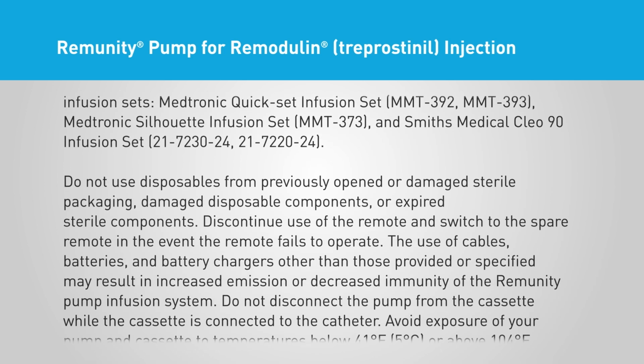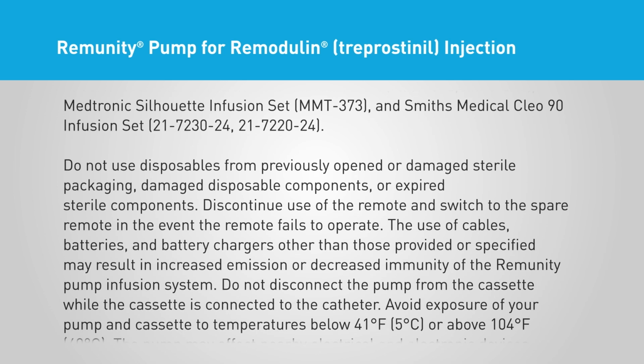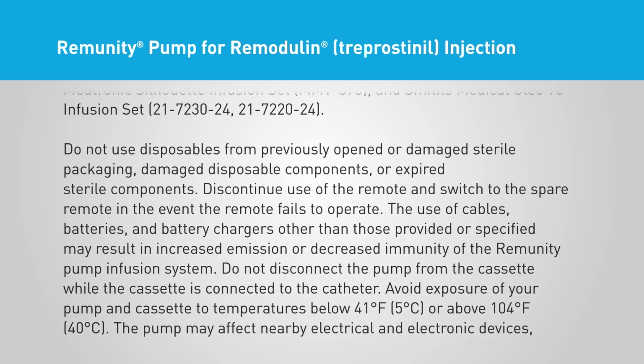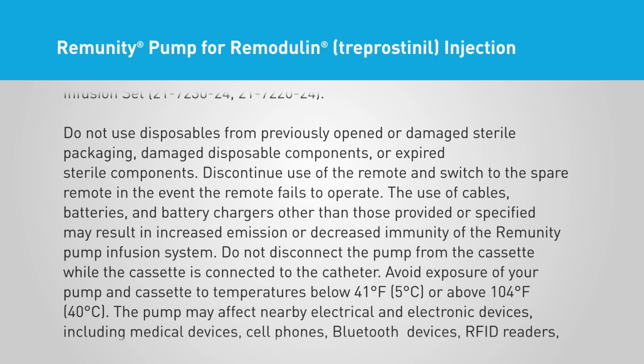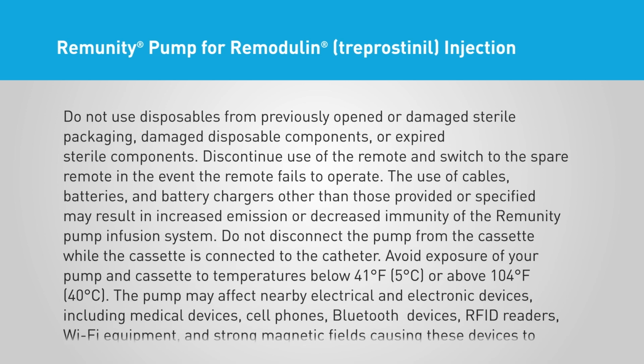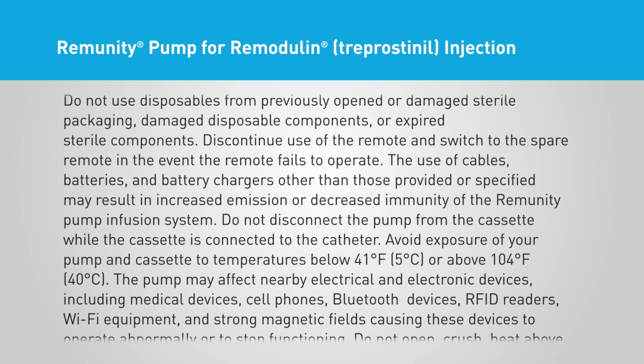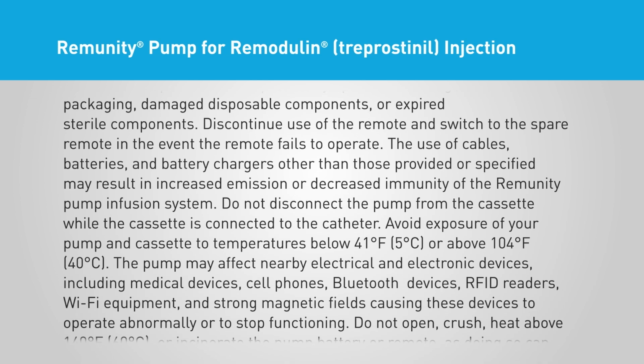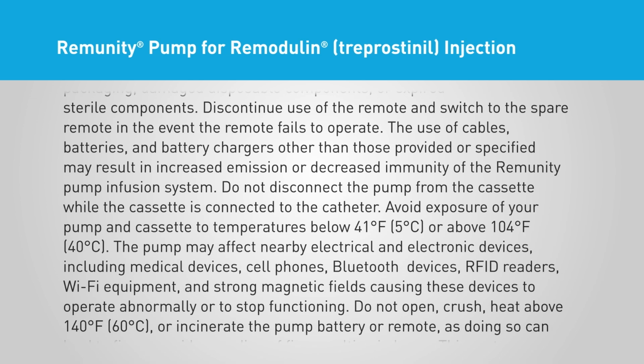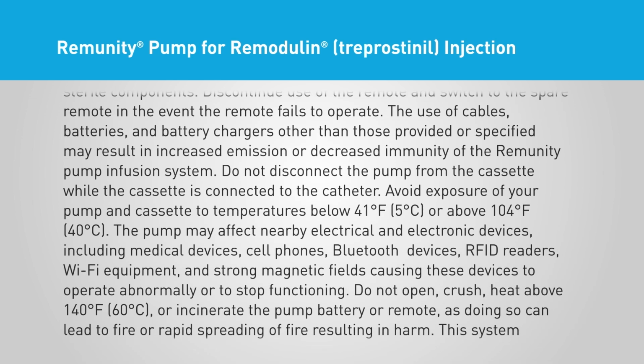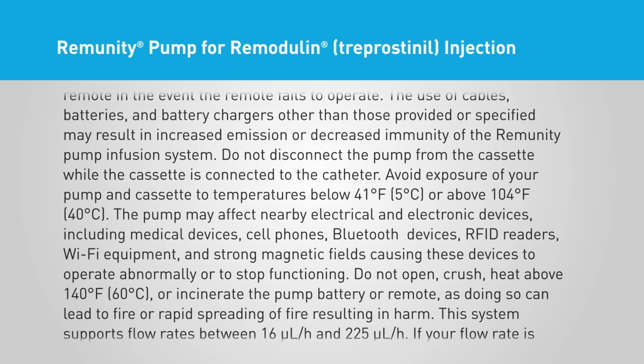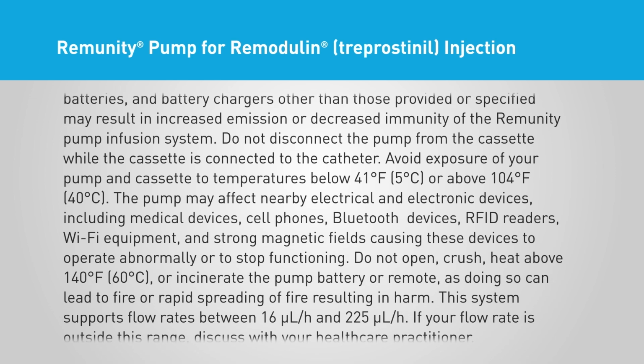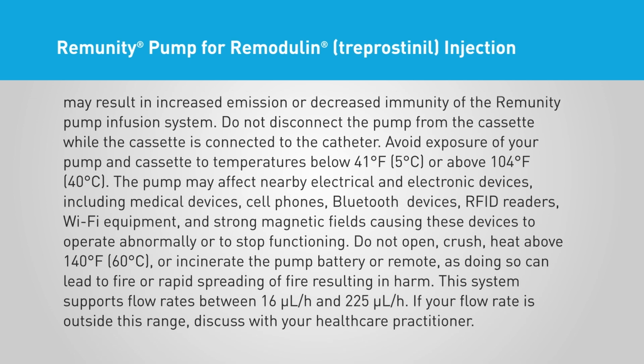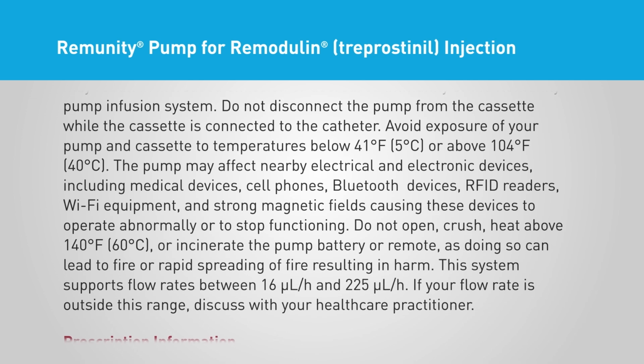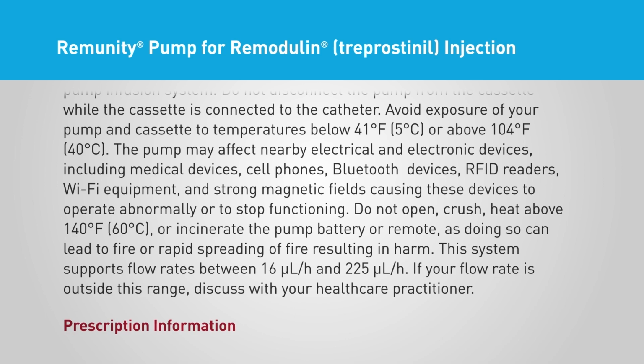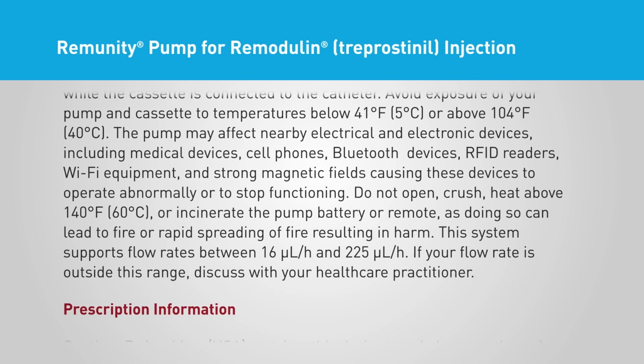Discontinue use of the remote and switch to the spare remote in the event the remote fails to operate. The use of cables, batteries, and battery chargers other than those provided or specified may result in increased emission or decreased immunity of the Remunity Pump infusion system. Do not disconnect the pump from the cassette while the cassette is connected to the catheter. Avoid exposure of your pump and cassette to temperatures below 41 degrees Fahrenheit, 5 degrees Celsius, or above 104 degrees Fahrenheit, 40 degrees Celsius. The pump may affect nearby electrical and electronic devices, including medical devices, cell phones, Bluetooth devices, RFID readers, Wi-Fi equipment, and strong magnetic fields, causing these devices to operate abnormally or to stop functioning.